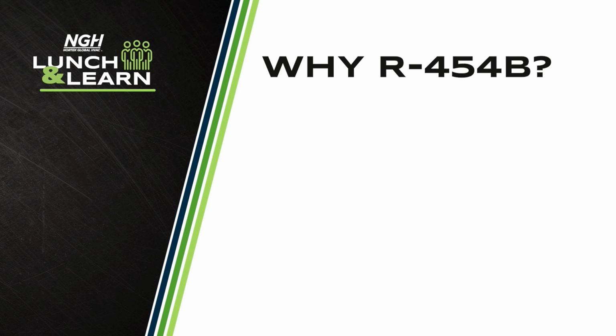There were a few different options, but it pretty much boiled down to two refrigerants, R32 and R454B. Our engineering team reviewed thermal properties, operating pressures, as well as GWP values, and we decided R454B was the way to go. One of the major reasons we settled on R454B was the low GWP number. R32 has a GWP of 675, just below the upcoming requirement. R454B has a GWP of around 450, which is well below the new metric for regulatory compliance.